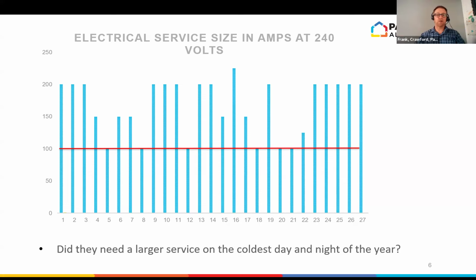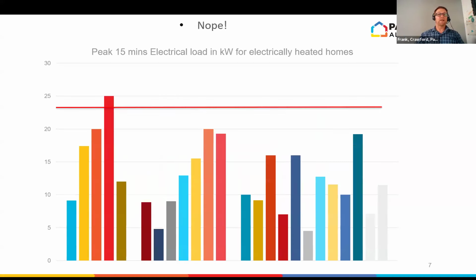Okay, so did they need a larger one on that coldest day of the year when it got down to -46 Celsius in some locations? The answer is generally no. So the red line on this graph is 24 kilowatts. And that is the theoretical instantaneous 100 amps times 240 volts that could be flowing from the grid into the house. Now, if it went for too long a time, there would be a reduction to 80% of that, but we're taking 24 as a theoretical.